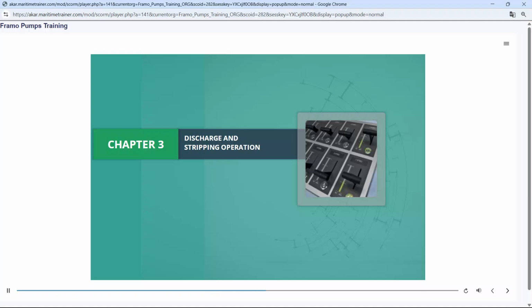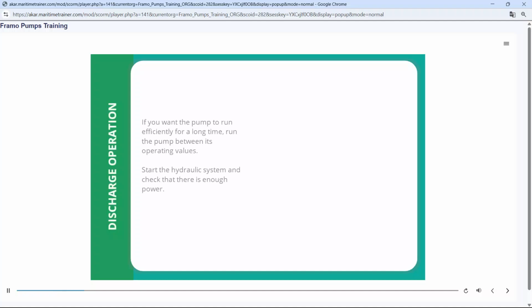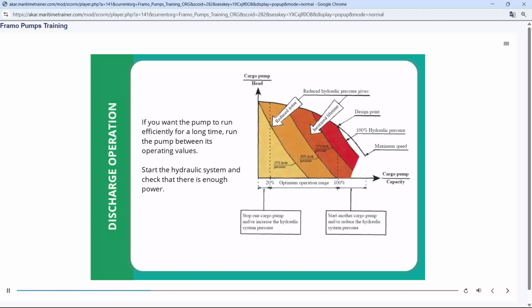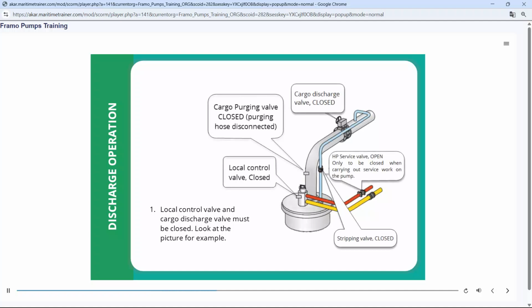Chapter 3. Discharge and stripping operation. Discharge operation. If you want the pump to run efficiently for a long time, run the pump between its operating values. Start the hydraulic system and check that there is enough power. The local control valve and cargo discharge valve must be closed. Look at the picture for an example.